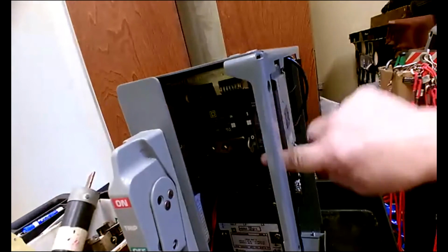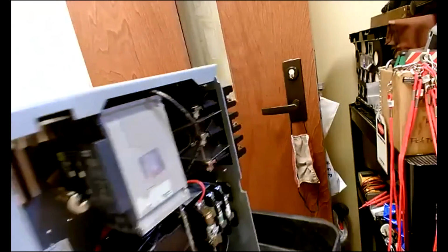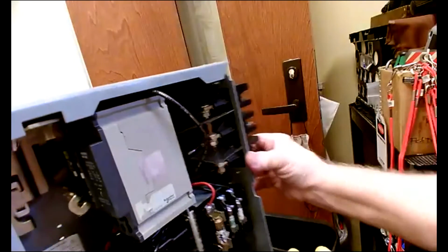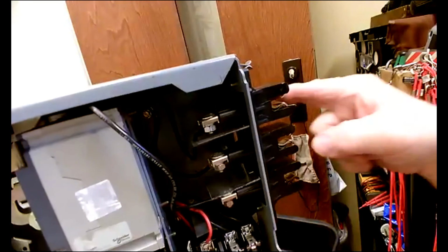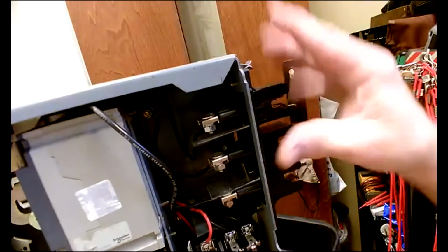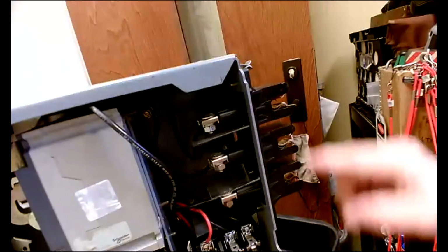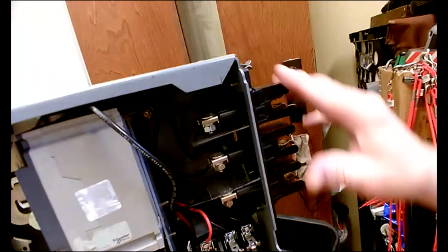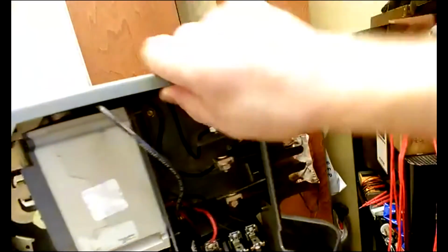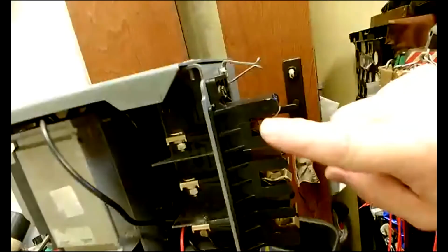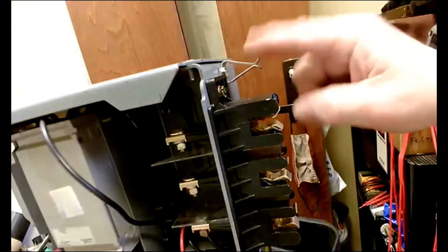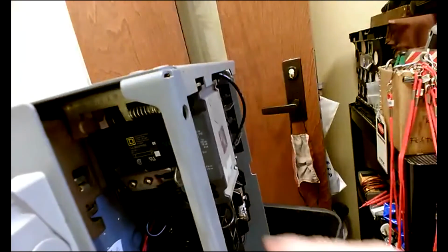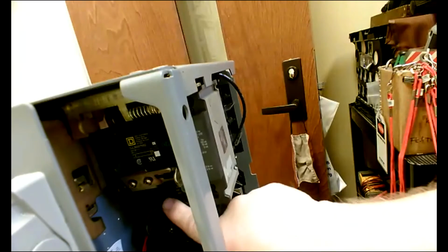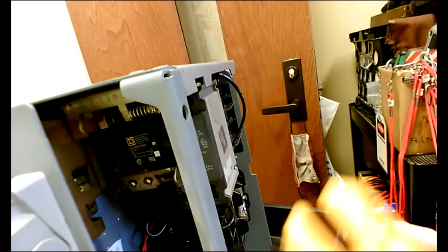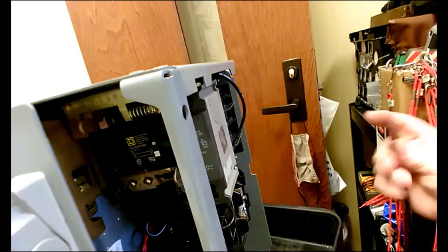The circuit breaker that's in here, the power comes in to the back where it plugs into a wall structure. These clips back here, this whole box plugs into a set of hot bus bars in a motor control center. And you've got here like three hot wires and a ground. So if, from the inside there, I measure from each of those three hot legs at the bottom of that breaker and go to ground, then that should be an indication that it is dead. Okay.